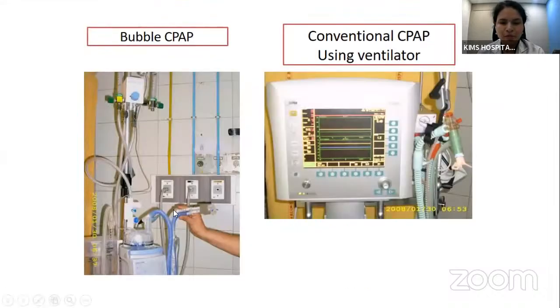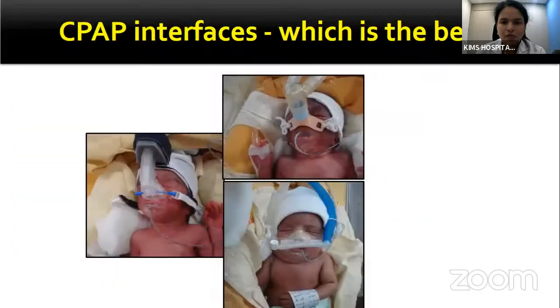So the figure on the left demonstrates bubble CPAP, whereas the figure on the right demonstrates one of the ventilators that can be used to deliver CPAP. The ventilator CPAP uses the expiratory valve of the ventilator to provide resistance during expiration, which is used for delivering positive end expiratory pressure. So having discussed the different CPAP systems, there is not much difference in the efficacy of one system versus the other. And for most practical reasons and for feasibility advantage, most of us prefer to use the bubble CPAP, which is one of the modes of constant flow CPAP.